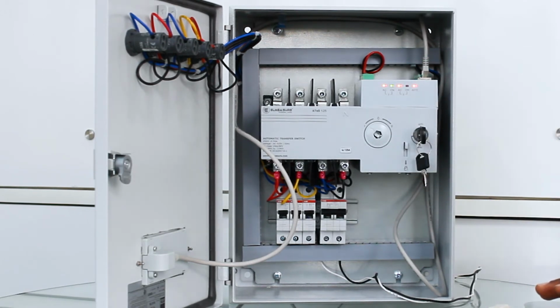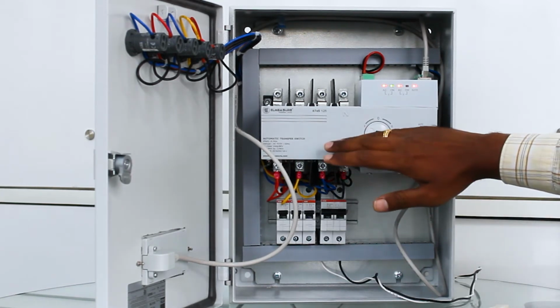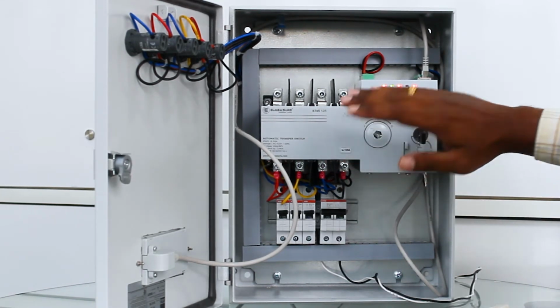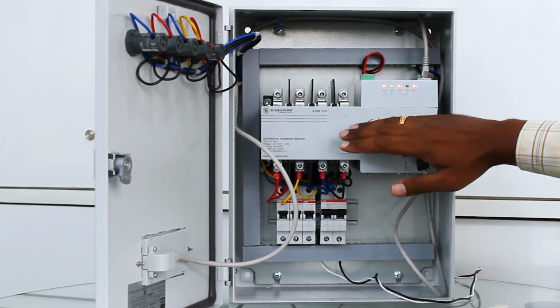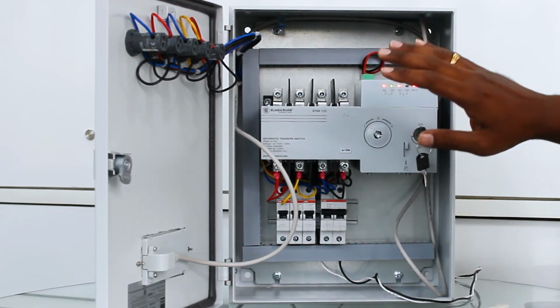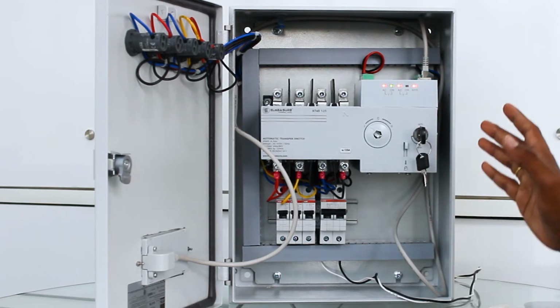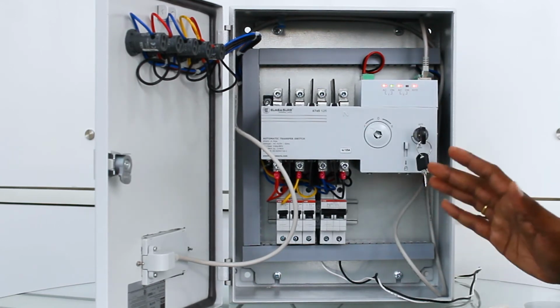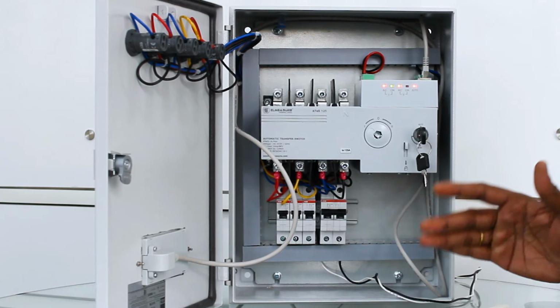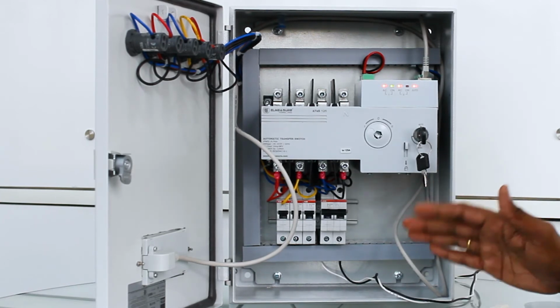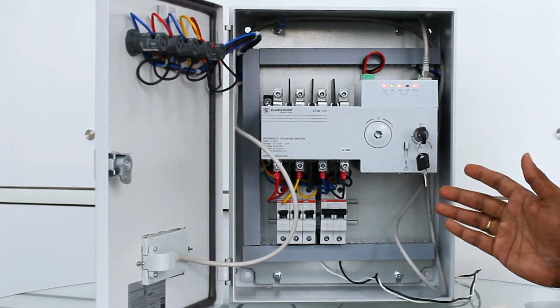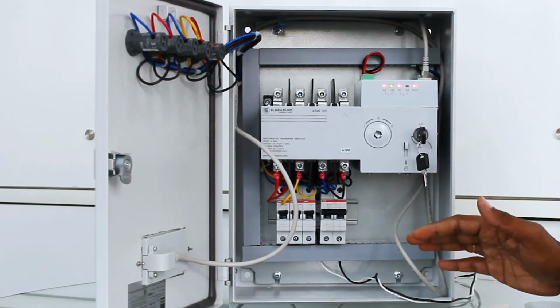In this device we have 3 modes of operation. Normally in the market everyone is providing a remotely operated ATS, but in this product we have 3 modes of operation. One is auto mode. Auto mode means it is a self-powered ATS, so everything will be automatic. If the primary source fails, the generator start is automatic, as well as the changeover, which will happen automatically.